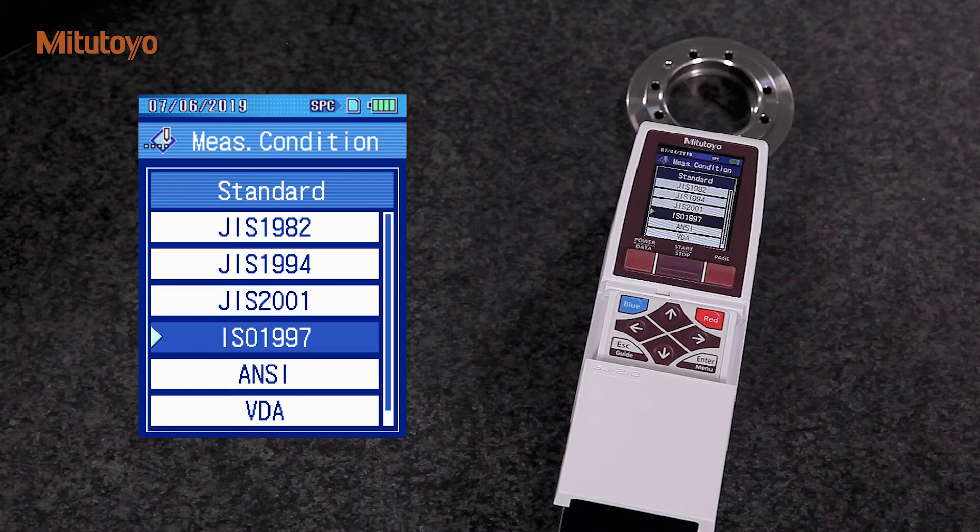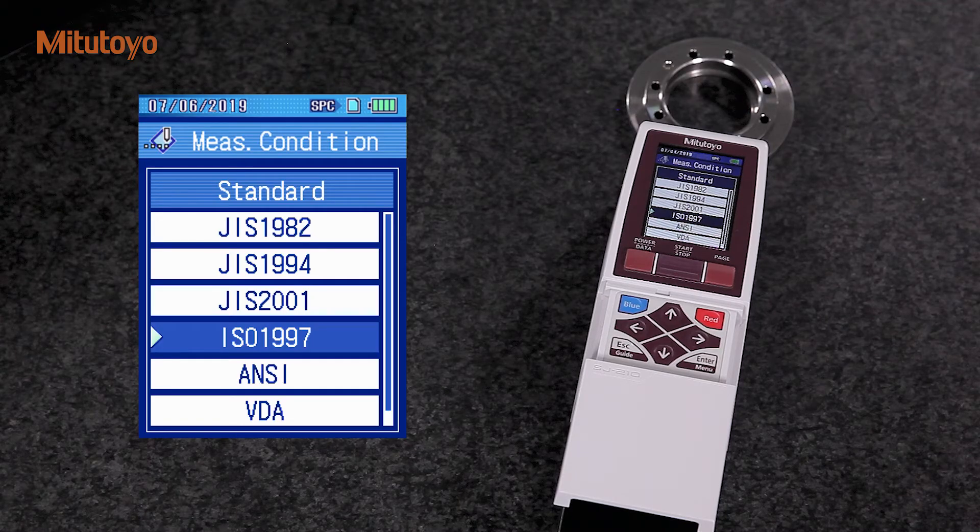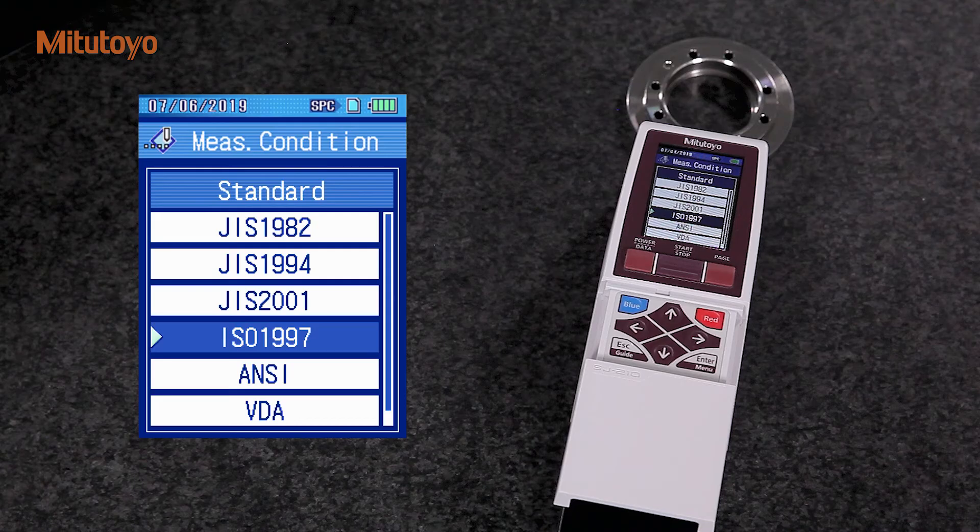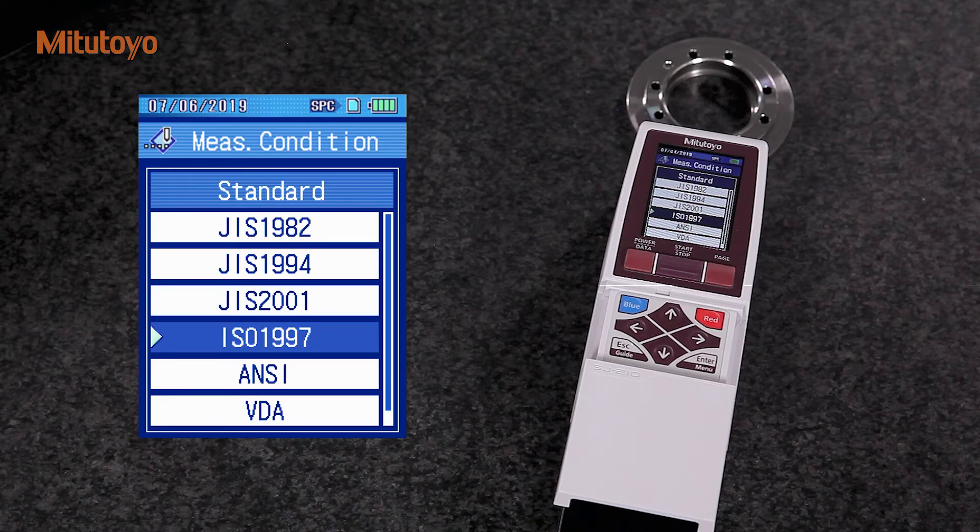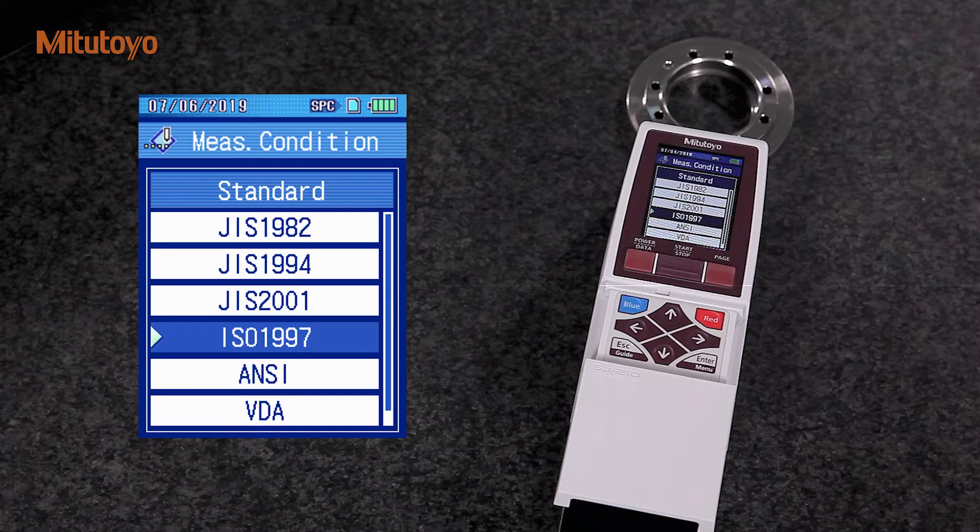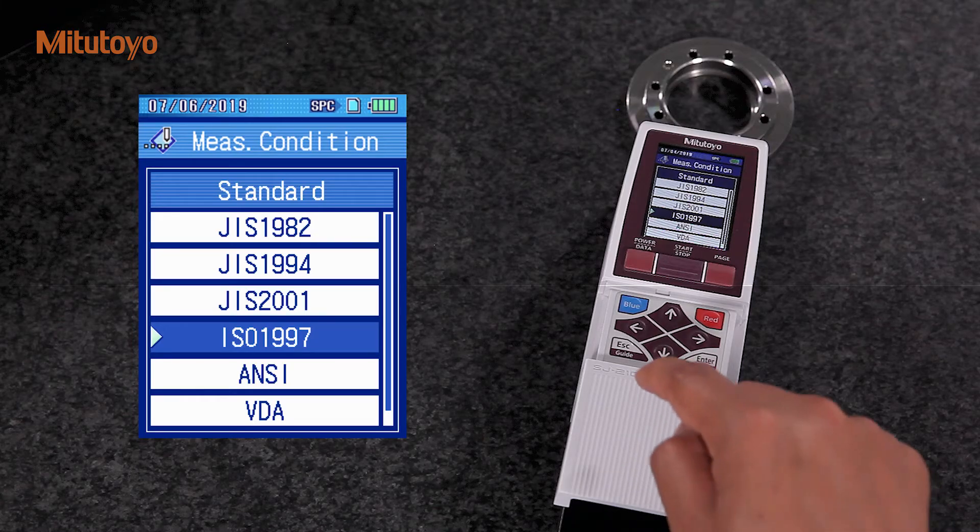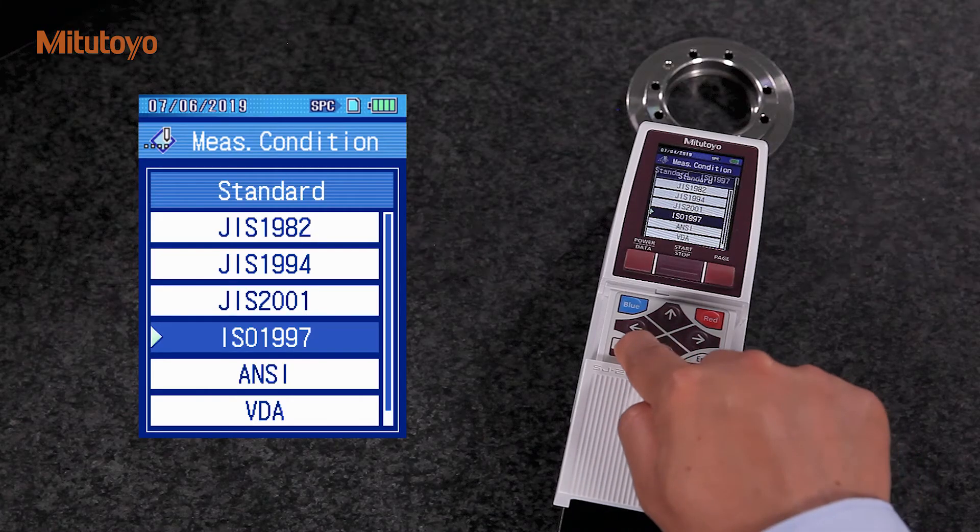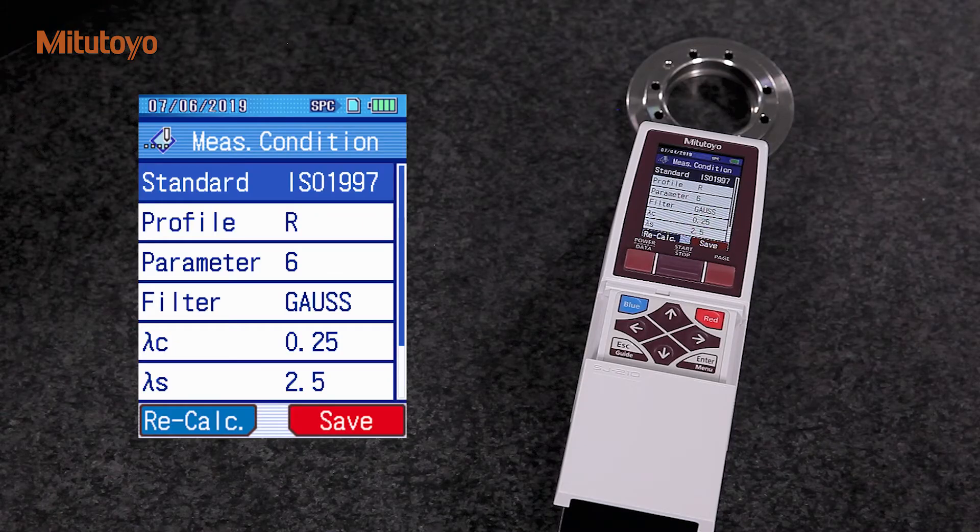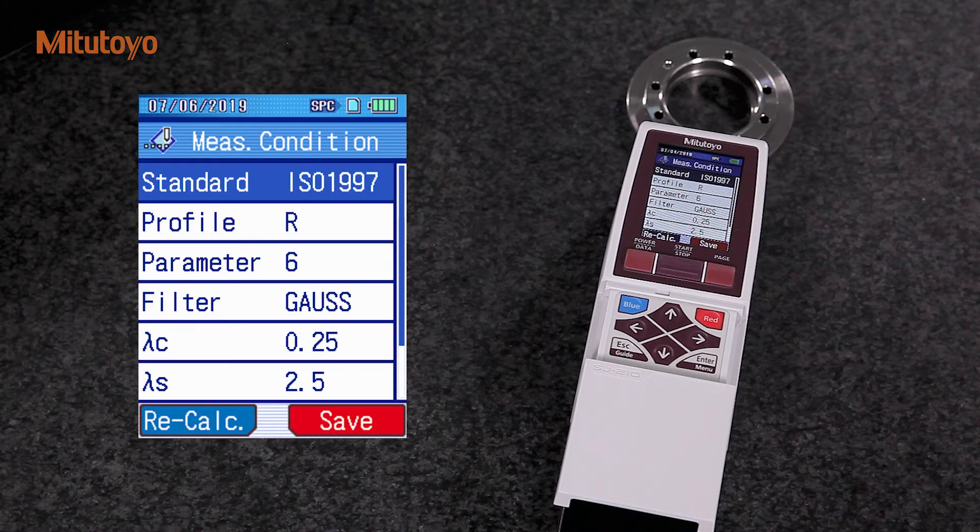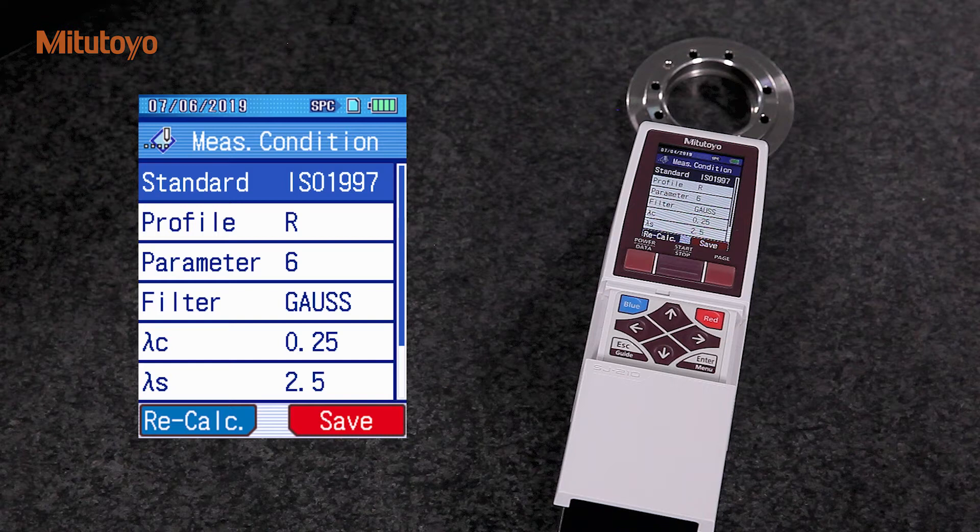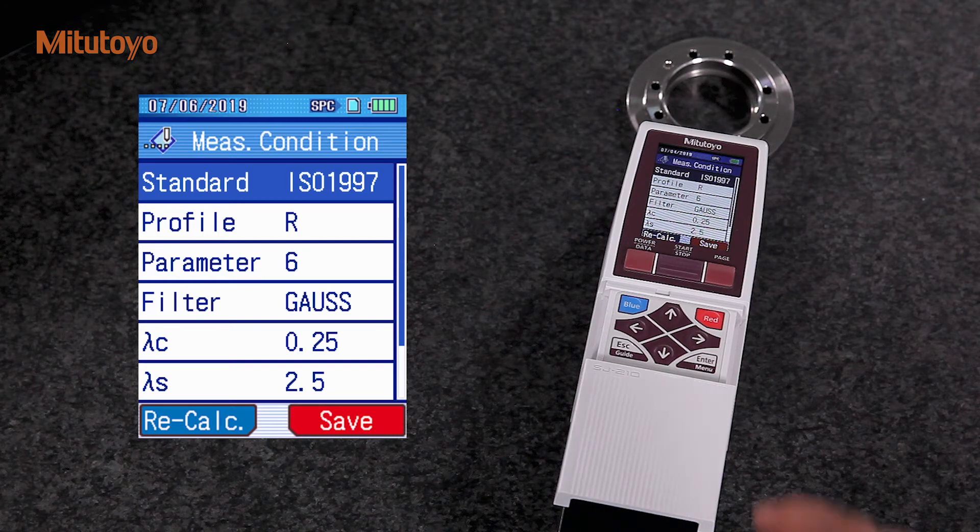Mitutoyo SJ-210 supports various industrial standards. For this measurement, we select an ISO standard. Now, we choose the required profile. We will measure surface roughness, so we select R profile.